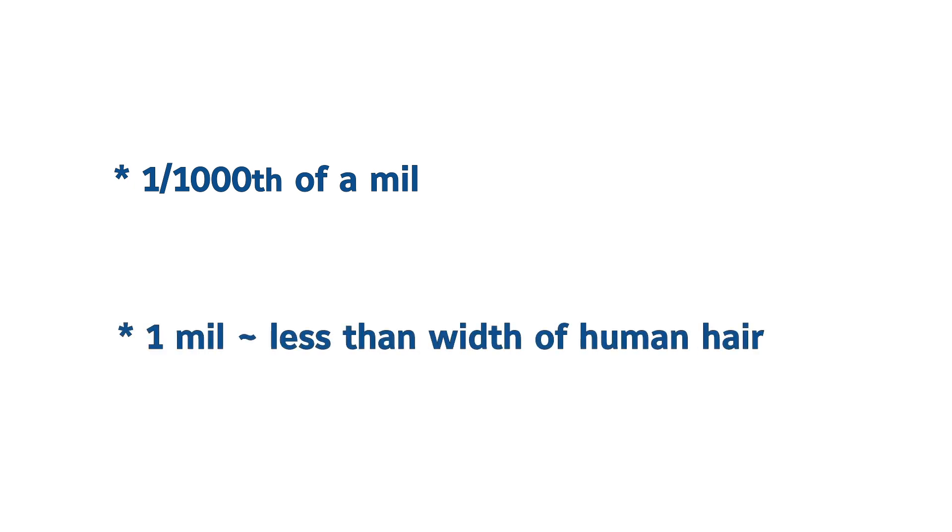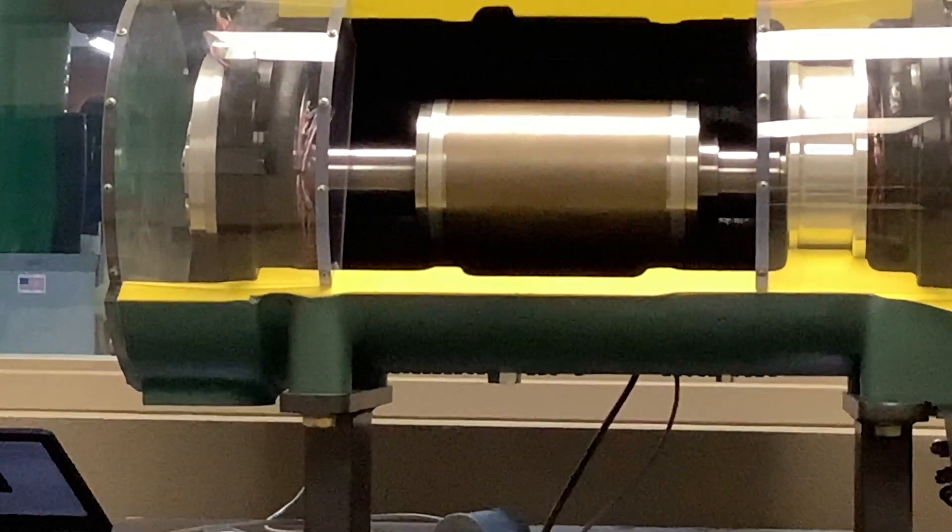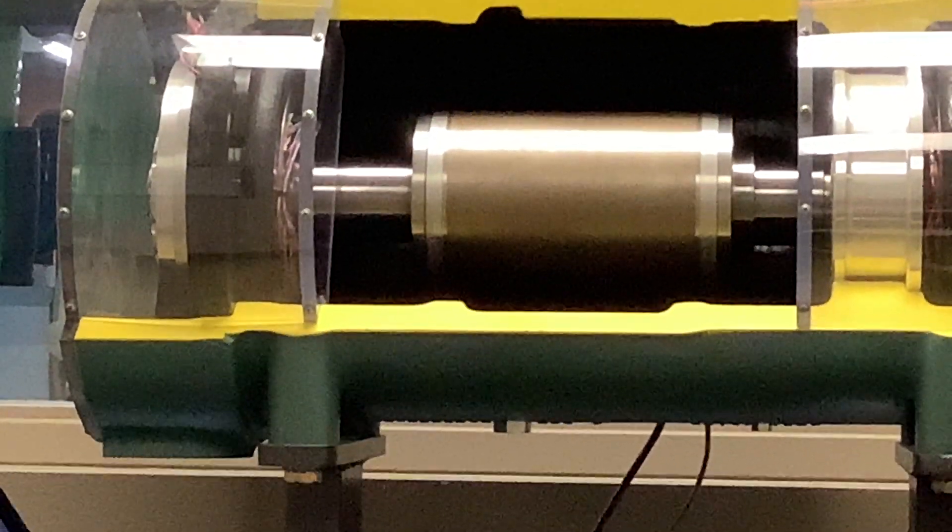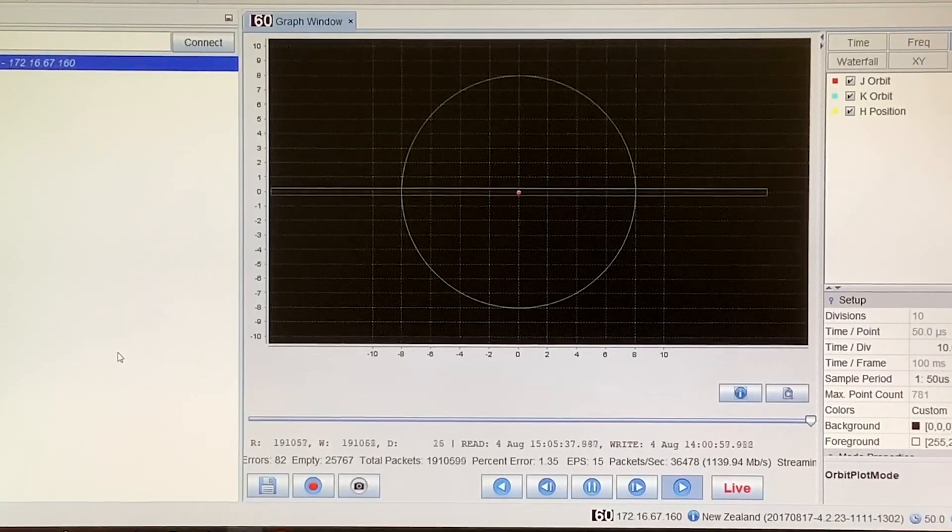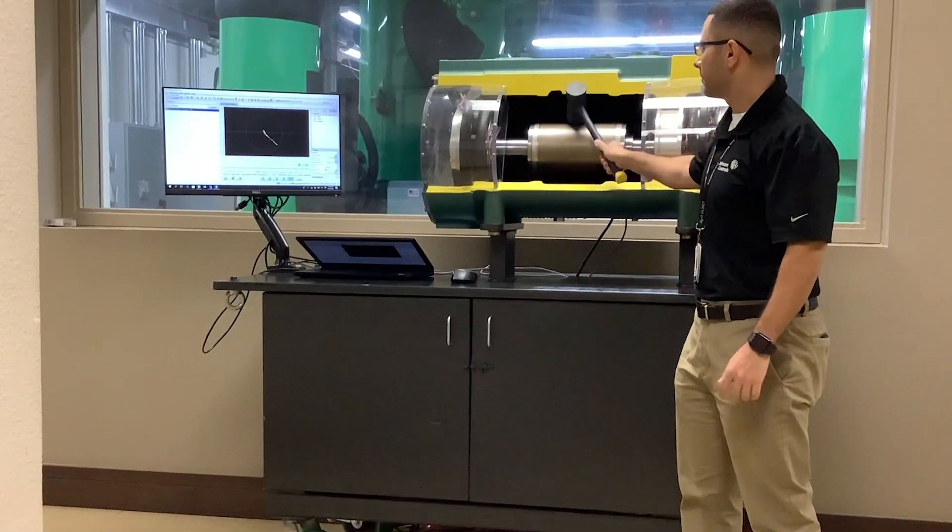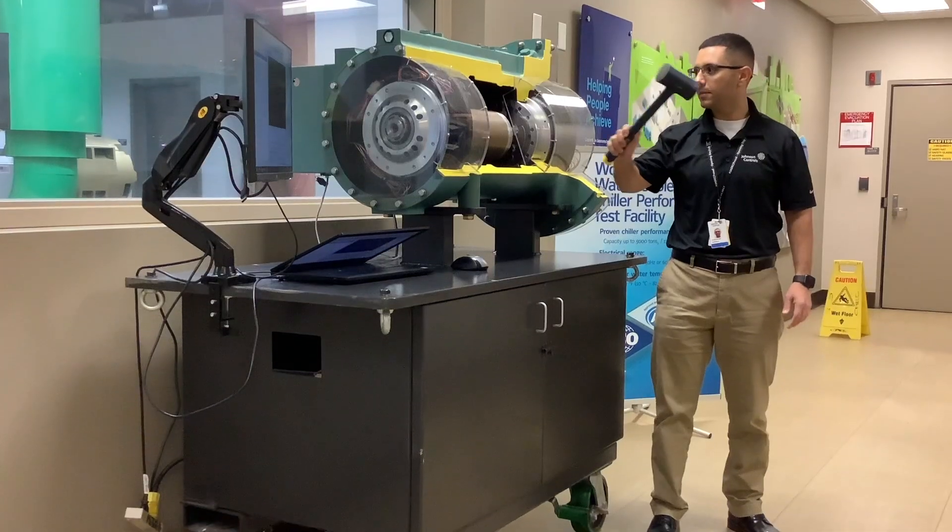The controller adjusts the output of the magnet 20,000 times a second to hold position. So when the assembly is hit and drops, you can instantly see on the monitor that the controller gets the assembly back to the friction-free field.